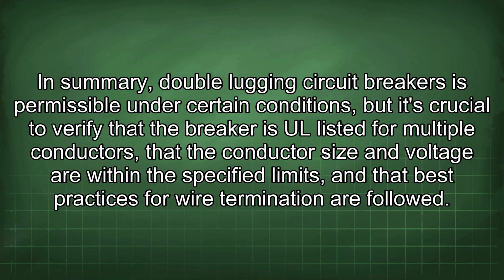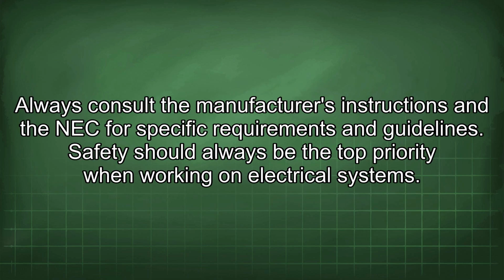In summary, double lugging circuit breakers is permissible under certain conditions, but it's crucial to verify that the breaker is UL listed for multiple conductors, that the conductor size and voltage are within the specified limits, and that best practices for wire termination are followed. Always consult the manufacturer's instructions and the NEC for specific requirements and guidelines. Safety should always be the top priority when working on electrical systems.